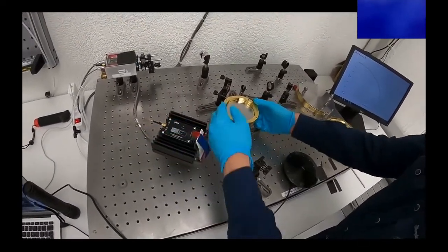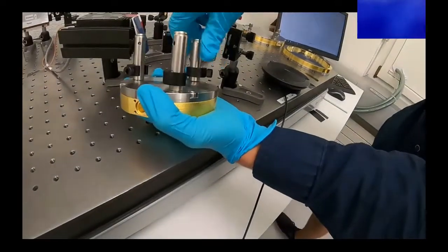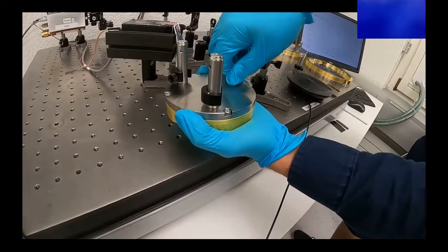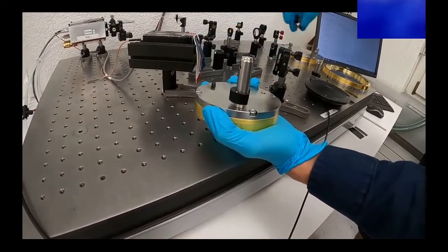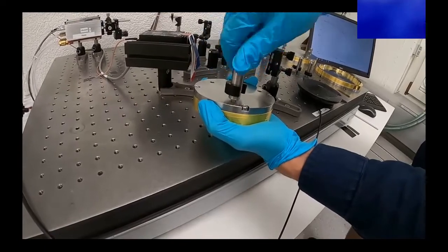Right, so now we will remove this cell. If you look at it from the bottom, we have it mounted on 3 posts that are set to a certain height. We will take them off now, so these are basically the 3 M6 threads that you can use to mount the cell in your setup. I will use these posts to mount the other cell, and this is basically the first thing you would have to do, and that is make sure that your cell is at the correct height, and also that it is parallel to your optical setup.